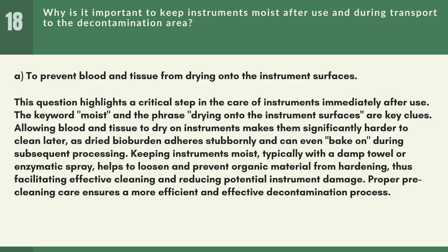Keeping instruments moist, typically with a damp towel or enzymatic spray, helps to loosen and prevent organic material from hardening, thus facilitating effective cleaning and reducing potential instrument damage. Proper pre-cleaning care ensures a more efficient and effective decontamination process.